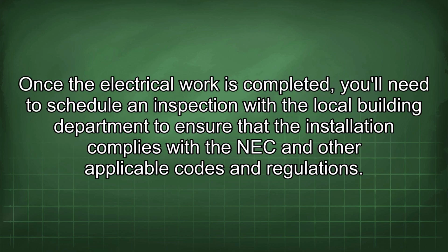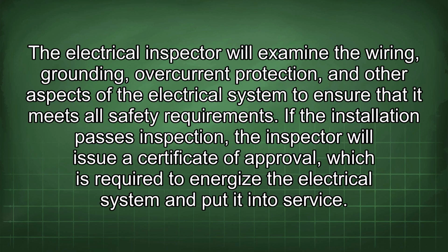Once the electrical work is completed, you'll need to schedule an inspection with the local building department to ensure that the installation complies with the NEC and other applicable codes and regulations. The electrical inspector will examine the wiring, grounding, overcurrent protection, and other aspects of the electrical system to ensure that it meets all safety requirements. If the installation passes inspection, the inspector will issue a certificate of approval, which is required to energize the electrical system and put it into service.